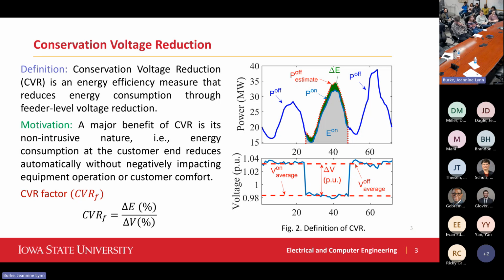And with CVR, you can see how it works. You reduce the voltage a little bit, usually a few percentage points, and it's expected that your energy consumption will be reduced. So this red dotted line is what it would look like if I didn't reduce voltage. Of course, I don't actually know what that would be, but if I know the difference between the two, that green area, that's the energy reduction due to the CVR.